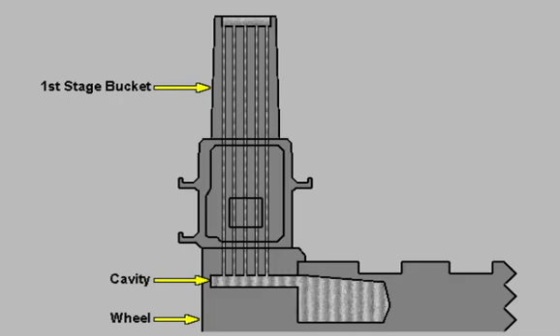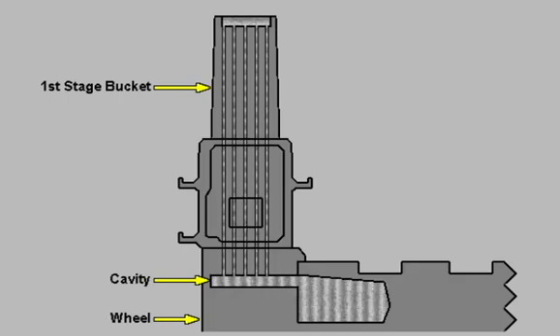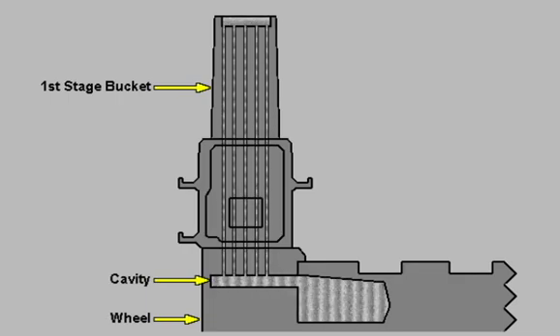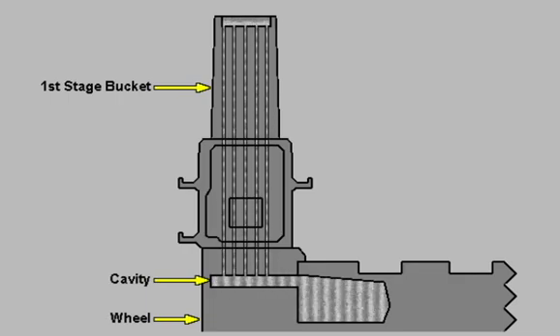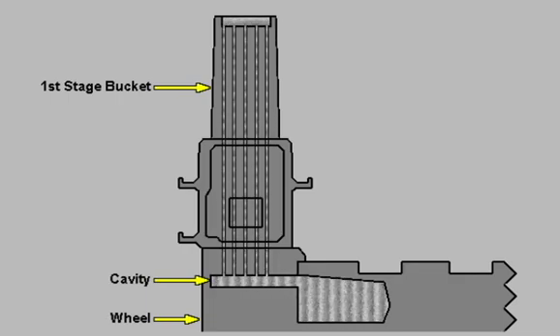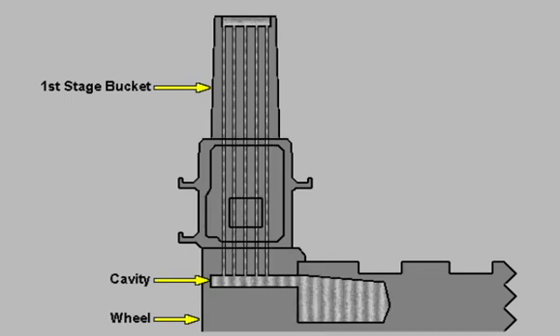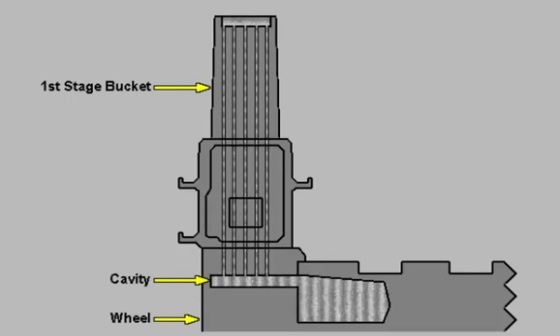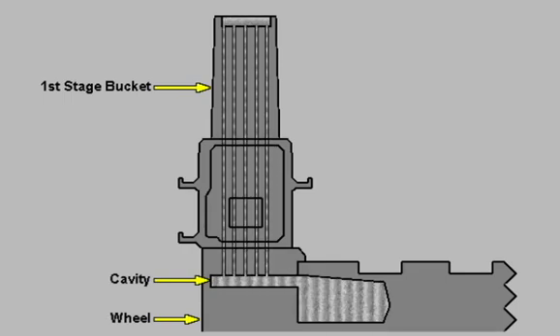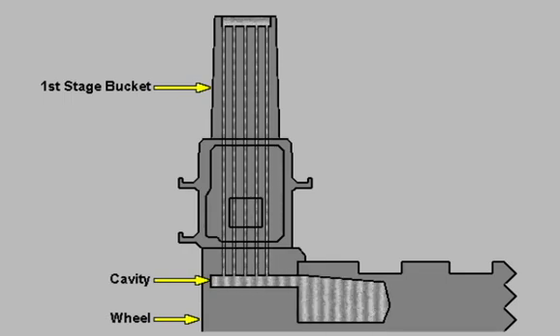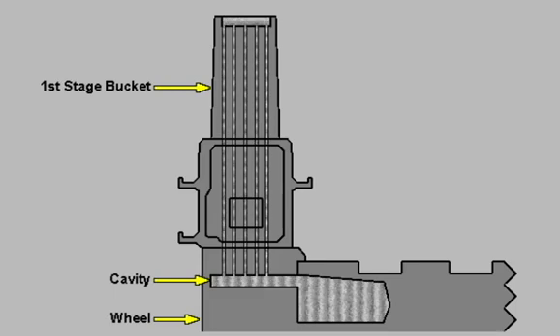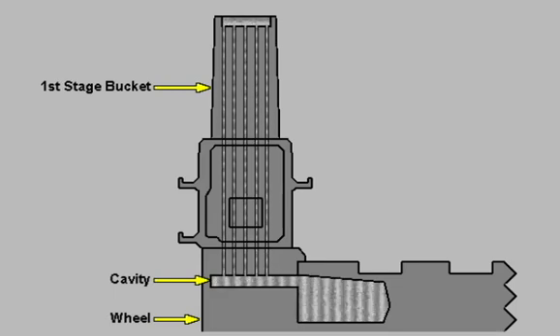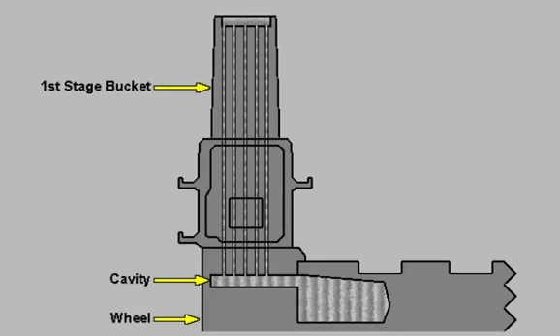Cooling air enters each first and second stage bucket through a cavity between the wheel and the base of the bucket dovetail. Cooling air flows through the longitudinal air passages and exits from holes at each recessed bucket tip.